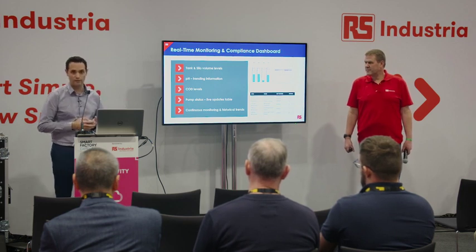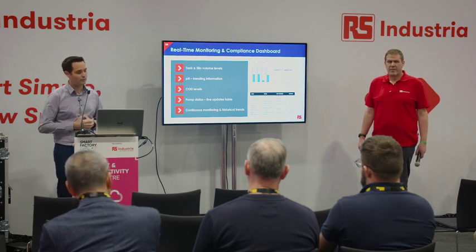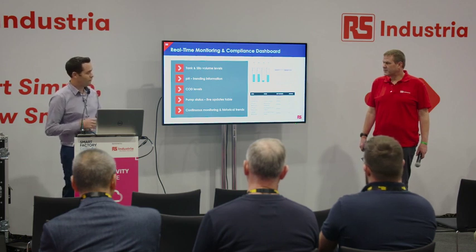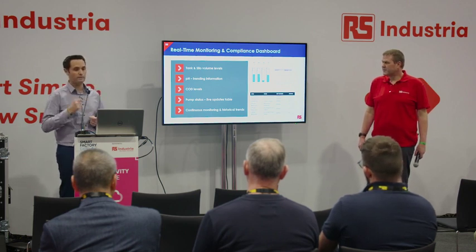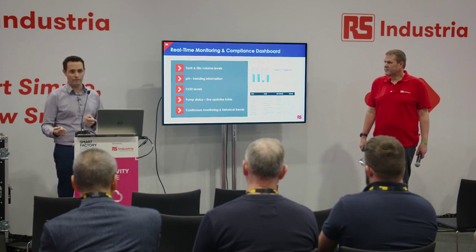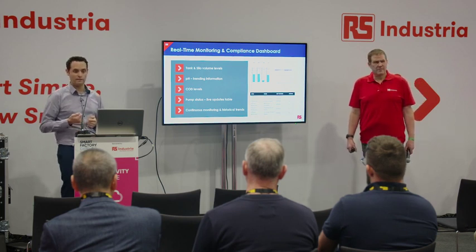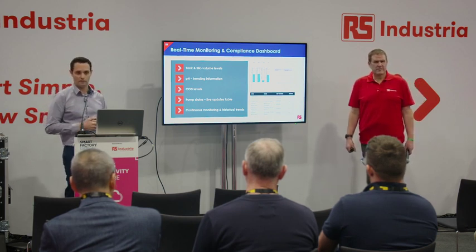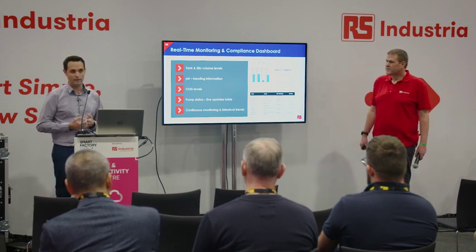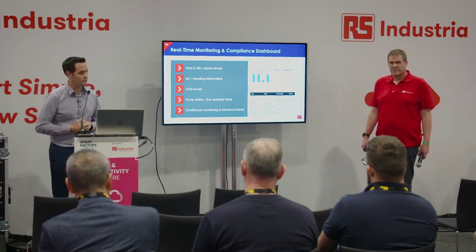The same for COD. We had a basic TOC analyzer in place, but we weren't able to take the data from it, harvest it and bring it together with all the other data streams. Through that, we were able to link up big COD demands that were hitting our plant with events in the factory, and then give the decision making and the data back to the factory so that we could start to challenge why we were losing this. Eventually every loss we had from a COD perspective was sugar, was product going down the drain, and eventually it was a cost-saving opportunity.